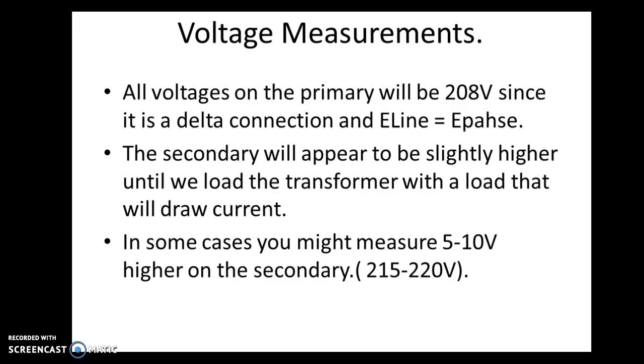Voltage measurements for this shop job: all voltage on the primary side will be 208 since it is a delta connected, E line to E phase system, or E line equals E phase in this system. The secondary will appear to be slightly higher until we load the transformer with a load that will draw current. So again, that secondary side has compensating turns of winding so that once we do draw some current on that and the losses become more significant, eddy current losses, magnetostriction, and so forth, we will get down to that usable 208. But before that, you might see 215 or 220 with no load connected.